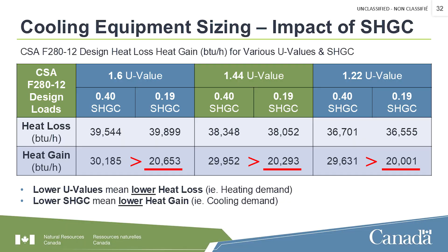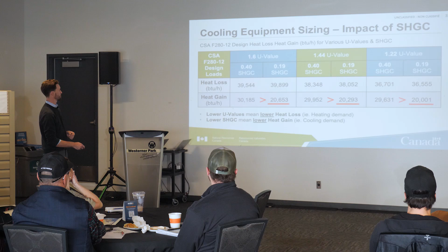So in all cases, going to a lower solar heat gain glass with this house that we're looking at today cuts the heat gain by about 1/3, which is pretty dramatic, right? 10,000 BTU, 9,000 BTU, that's nearly a ton of smaller cooling size required for this house. So as we make decisions early in our process of design to try and get to the optimal window, we're considering all of these things.